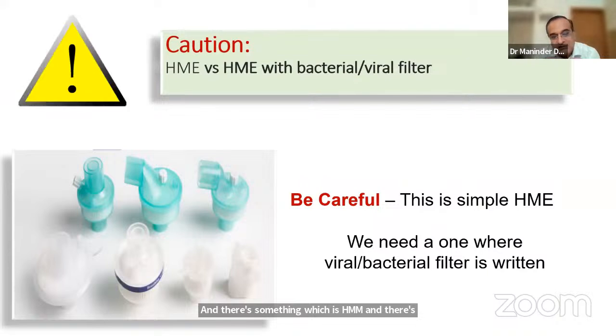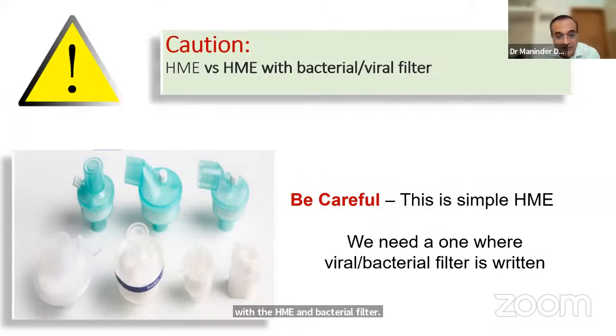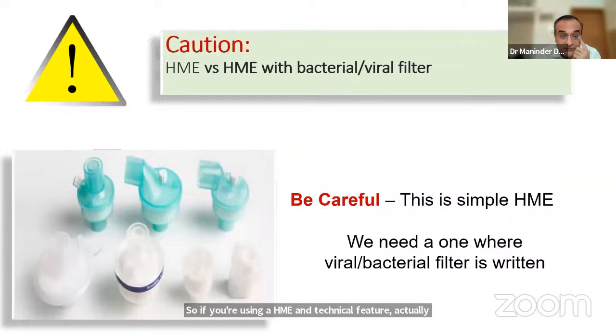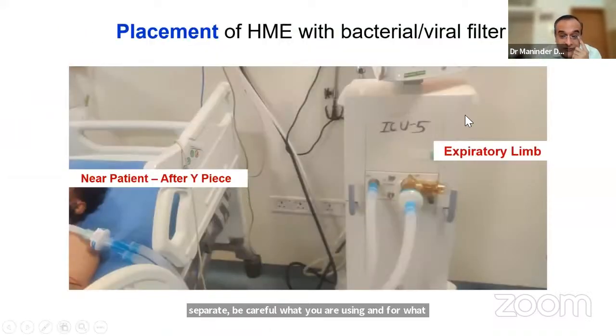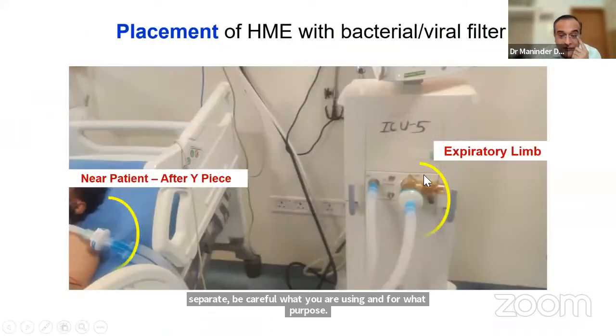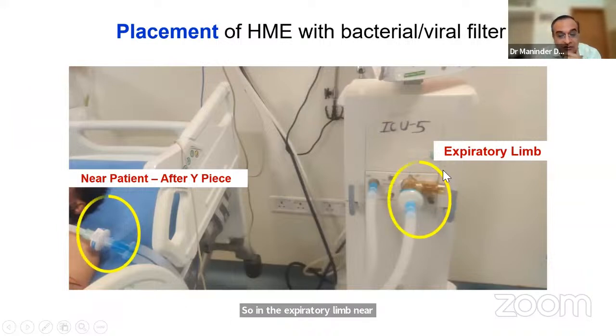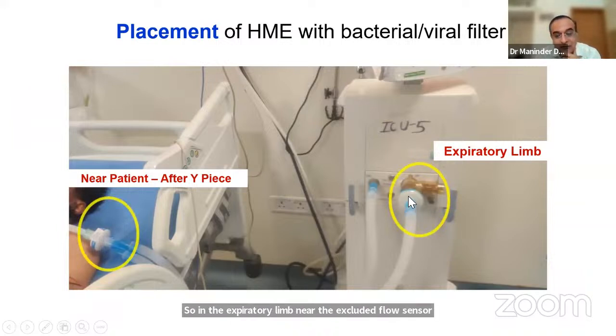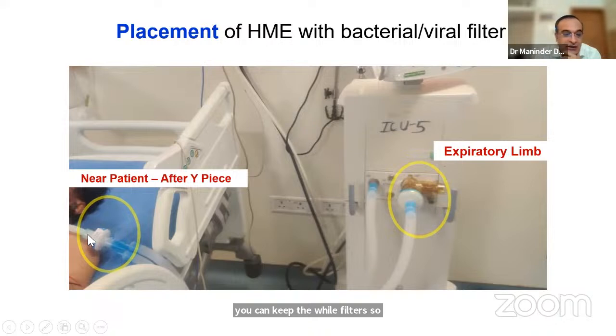If you're using an HME and bacterial filter separately, be careful what you're using and for what purpose. In the expiratory limb, near the expiratory flow sensor, you can keep the viral filters so that viruses and bacteria get trapped there. And near the patient, you can keep an HME if you want, which is a heat moisture exchanger.